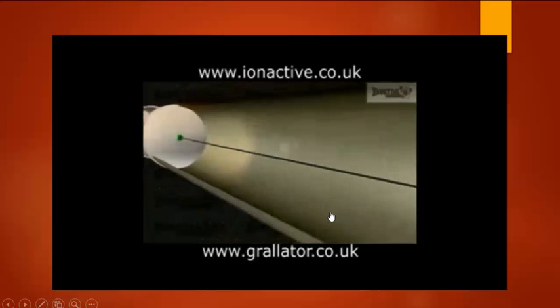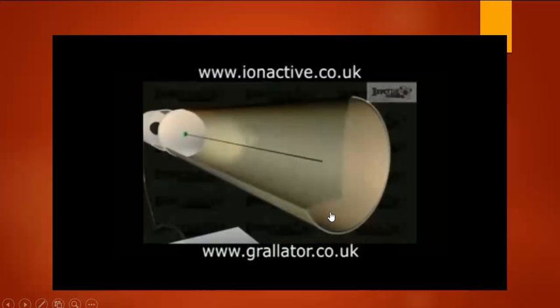The front of the tube is sealed with a radiation window that is specific to the type of radiation to be detected by the counter. For example, a thin mica window is used if the tube is to be sensitive to alpha particles and low-energy beta particles, both of which have low penetrating power. A thicker window, or a different material, such as glass or a thin sheet of metal, is used for high-energy beta particles, while for gamma rays the tube is often sealed without a window.